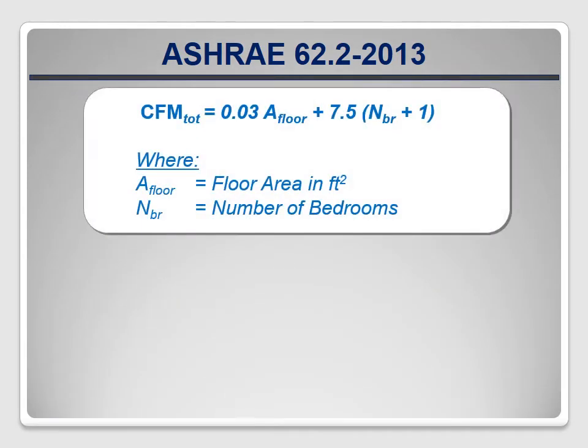ASHRAE 62.2 2013 includes an equation for CFM total, and it's based on the floor area of the dwelling and the number of bedrooms. The total desired ventilation rate is equal to 3 CFM for every 100 square feet of floor area plus 7.5 CFM for each occupant, assuming that there are two occupants in the master bedroom and one in each other bedroom. It'd be better to use the actual number of occupants, but for new construction that may not be known until after the house is built and put on the market.